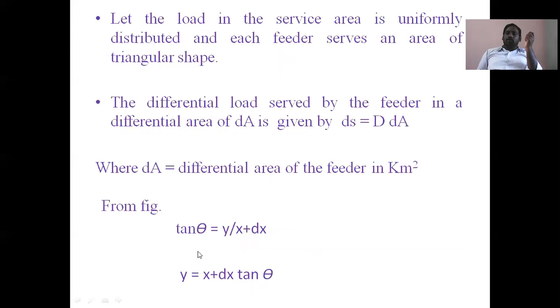This total load is located as a lump sum load at a point on the main feeder at a distance of 2/3 into Ln. That means the load can be located at 2/3 of the total length of the feeder, which can be expressed as 2/3 into Ln into k into Sn, because the load is located at 2/3 distance of the total length. K into Sn is an additional factor to describe the percentage voltage drop. This is the formula for percentage voltage drop. So Sn can be substituted in this equation: 2/3 k into D into Ln cube tan theta.